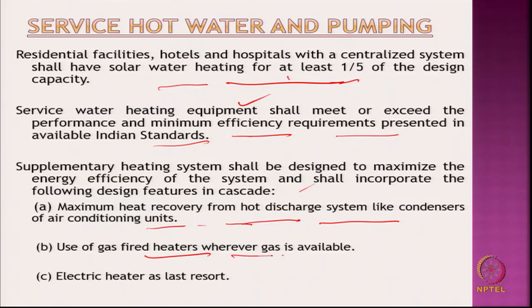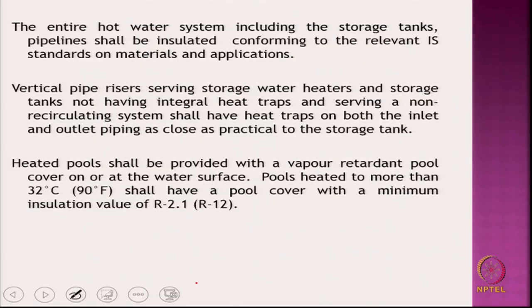Use a gas fired heater wherever gas is available, an electric heater is usually the last choice because of the efficiency and so on. The entire hot water system, which includes the storage tank and pipelines, as per design, shall have heat traps on both inlet and outlet, and heated swimming pools, if they are there, shall be provided with a vapor grade retardant pool cover.